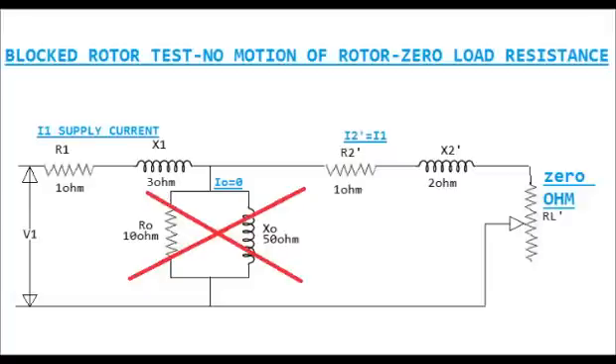In blocked rotor test, the load resistance is made 0. It is made 0 by blocking the rotor from rotating, so slip will be 1. As slip will be 1, RL dash will be 0.